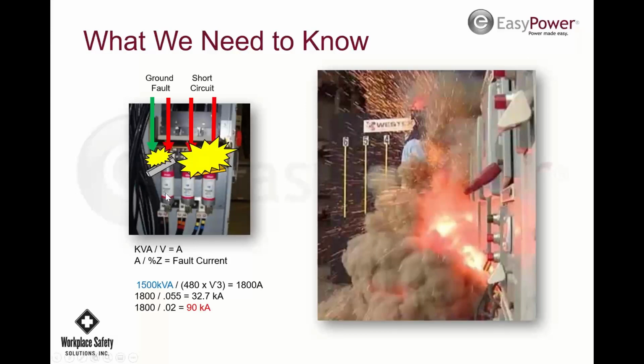If this were to happen on the single phase, on the low side, it probably would not ionize to a three-phase fault because the fuses would be fast enough to isolate it to that one single phase. Maybe, not always, but maybe, depending on the type of fuses you have. But up on this part, you're a distance away from a breaker probably, so it's definitely going to be enough time to cause this to go. I mean, I say definitely. It could be a fast-acting breaker, but it very likely would be a three-phase fault.